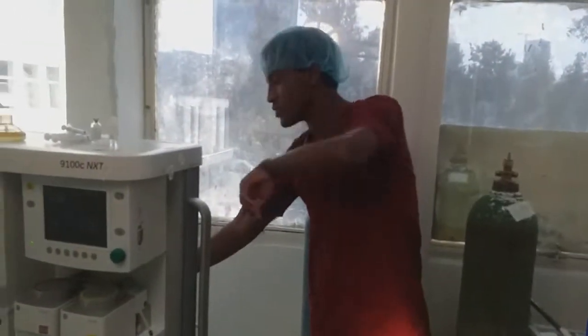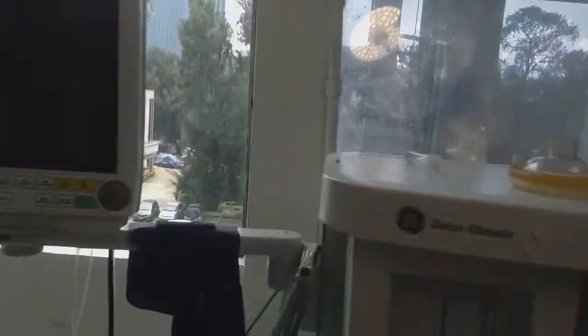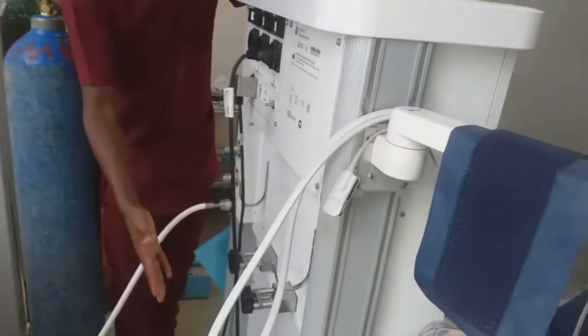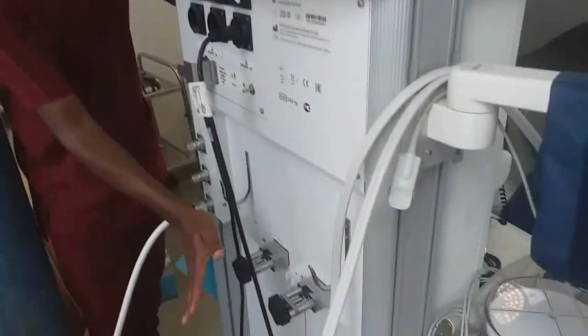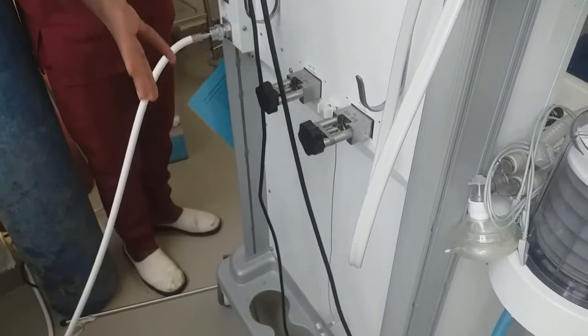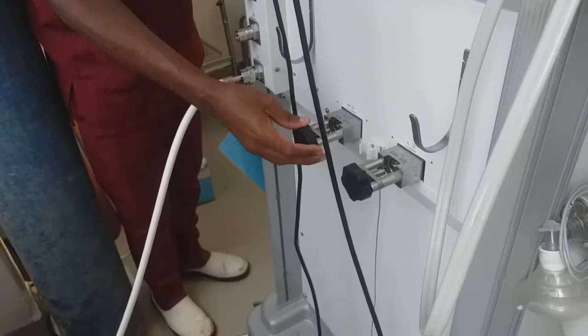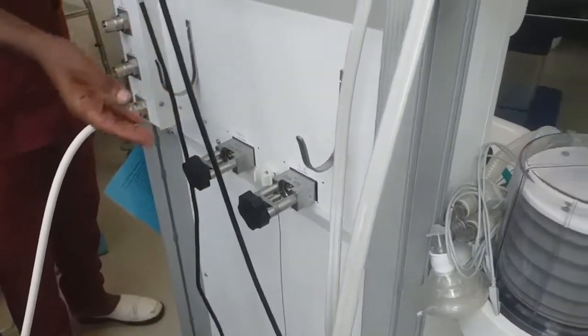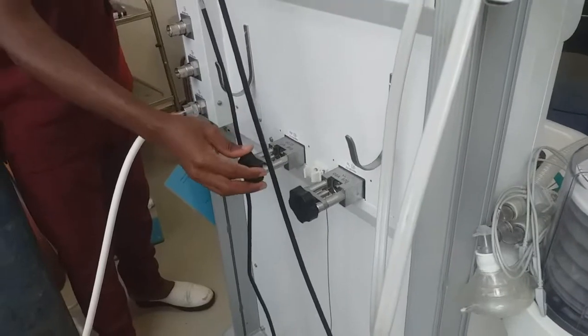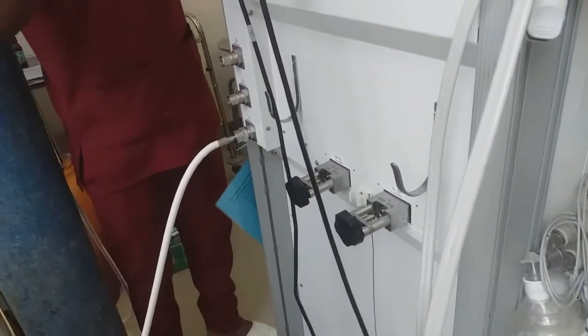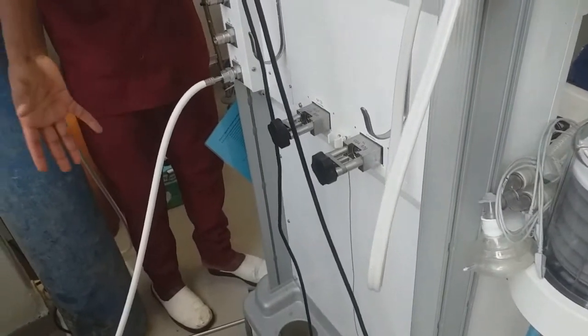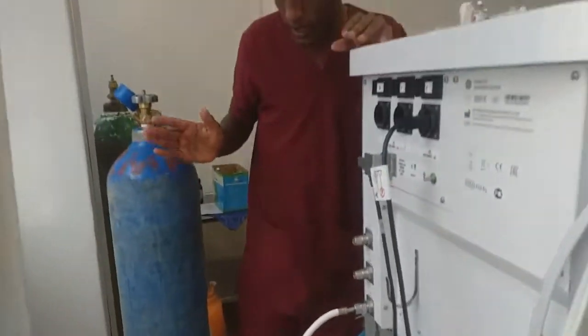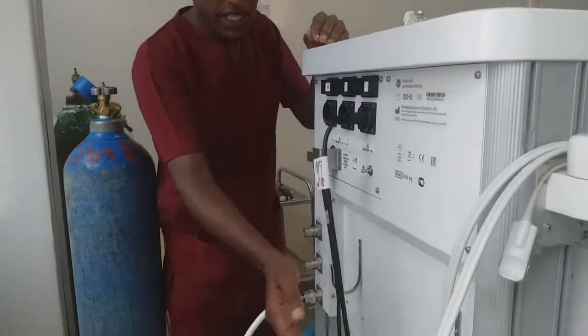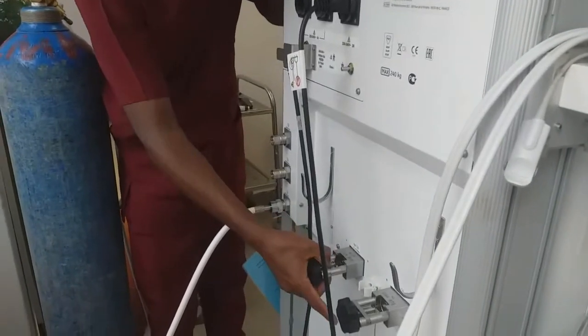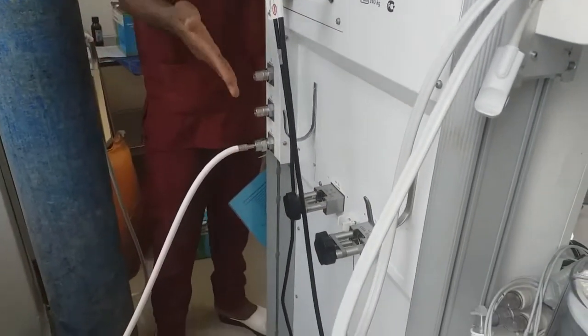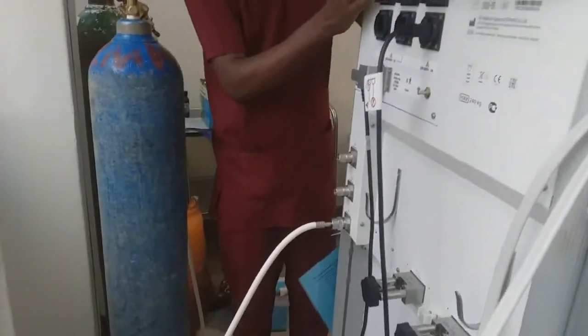Now I'm going to check. If it's present, best. But for now, we don't have an E-cylinder on this machine. This is the position of the E-cylinders. They have their own pin index system. If there is a technical error, such as an abnormal connection of an abnormal cylinder with an abnormal hole, their pin index system will prevent the disaster that could occur during the anesthesia procedure.